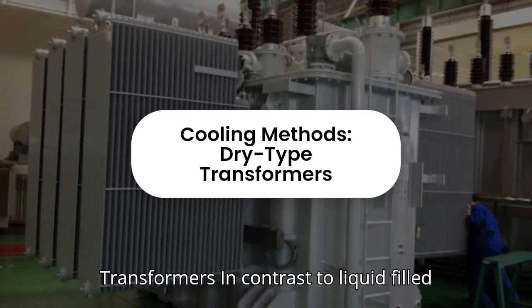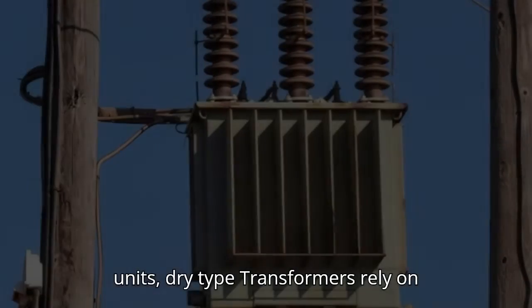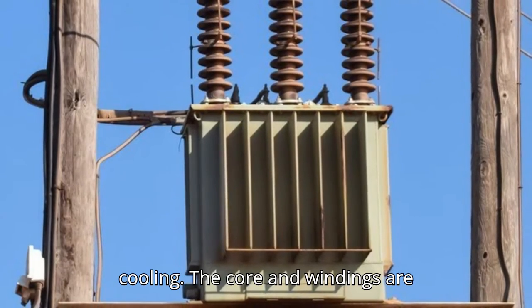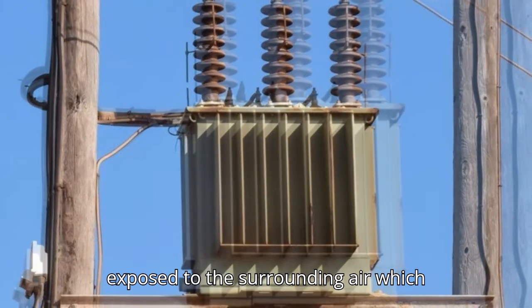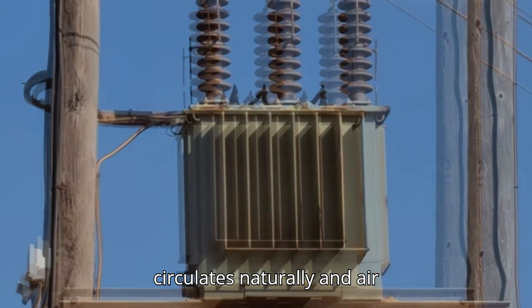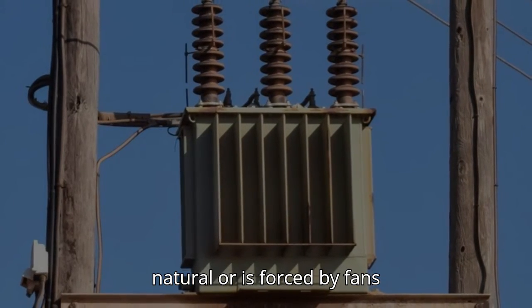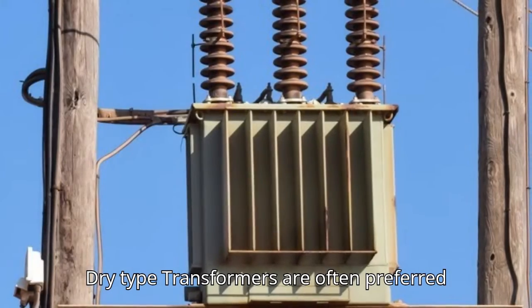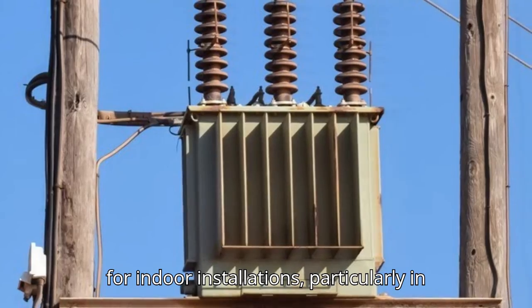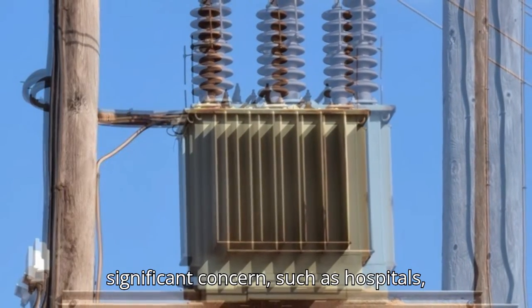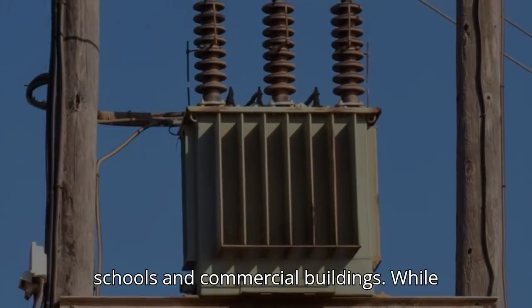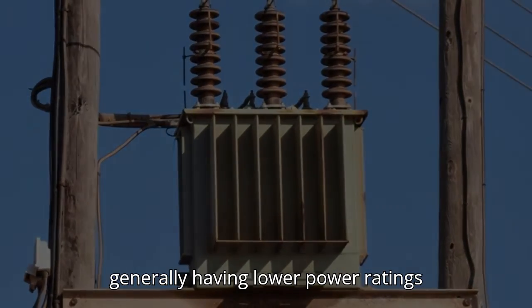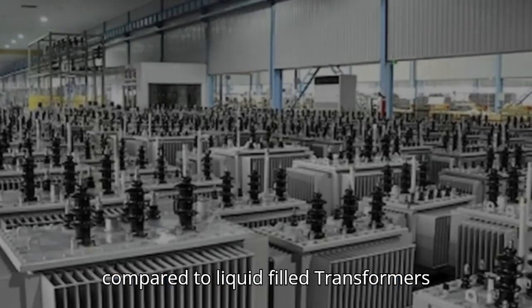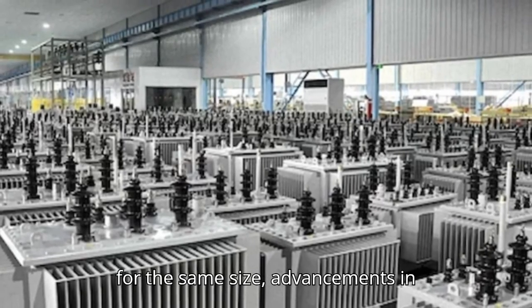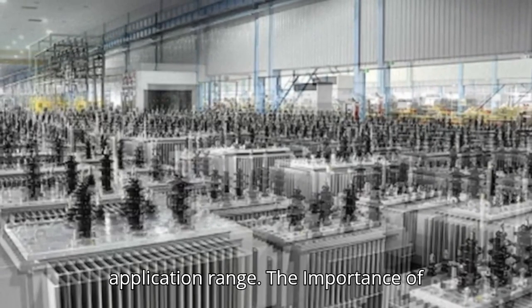Cooling methods. Dry-type transformers. In contrast to liquid-filled units, dry-type transformers rely on air or other non-flammable gases for cooling. The core and windings are exposed to the surrounding air, which circulates naturally (AN, air natural) or is forced by fans (AF, air forced) to remove heat. Dry-type transformers are often preferred for indoor installations, particularly in environments where fire safety is a significant concern, such as hospitals, schools, and commercial buildings. While generally having lower power ratings compared to liquid-filled transformers for the same size, advancements in insulation materials have expanded their application range.